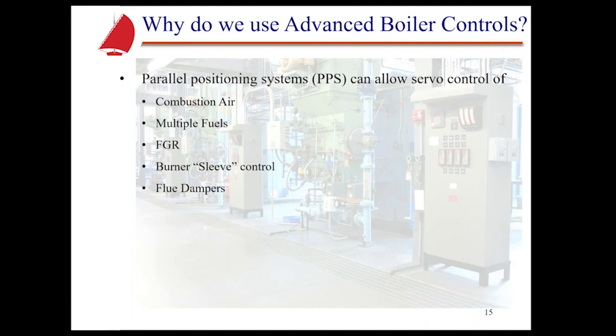And we actually designed and sell a complete system for that interfaces with our parallel positioning systems. So again, we may have the control itself, maybe the brains of the system, but the hands and the feet, the heart of the system goes back to those servos. Spend the time to make sure that when you're setting up this system, for instance, in a full closed position, that the servo isn't being mechanically stopped, it's being electrically stopped by the internal end-stop switch. That is a mistake that's made very, very many times. Same way on the full open position. Make sure that they're not mechanically binding, that they're actually being stopped by the internal switches. That's extremely important.